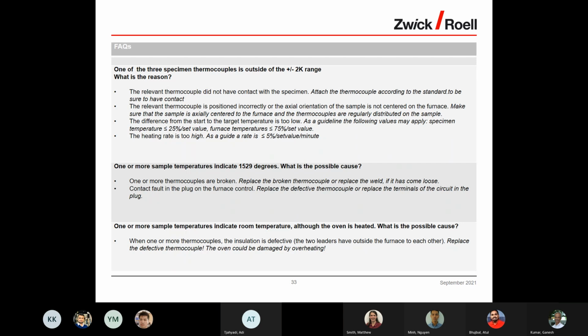The difference from the start to the target temperature is too low. As a guideline, the following values may apply. Specimen temperature 25% set value, furnace temperature 75% set value. The heating rate is too high. As a rate, 5% set value per minute.